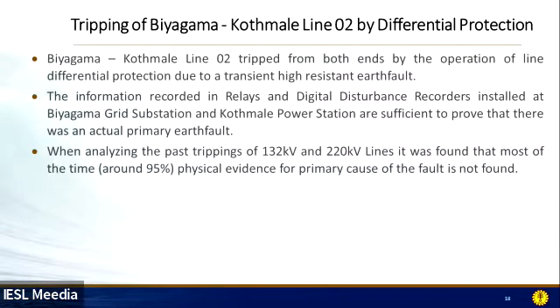So when analyzing the past trippings of 132 kV and 220 kV lines, it was found that around 95% of the time, physical evidence for the primary cause of the fault is not found. Only around 5% of the time have we been able to find some cause for a particular tripping, and our maintenance staff has to go to those locations and rectify that issue. Other than that, 95% of the time, the line faults recover themselves without any human intervention.